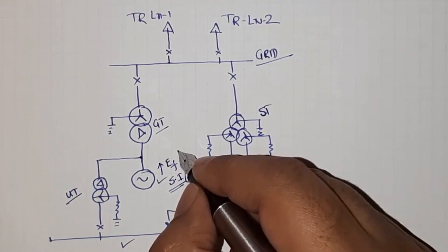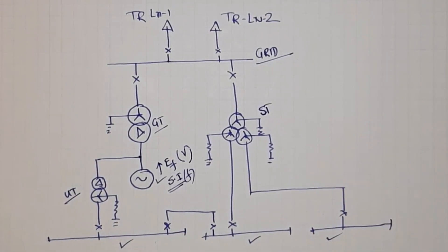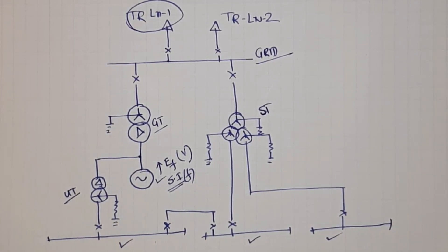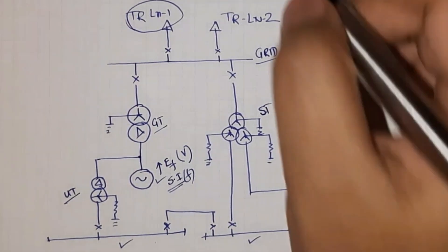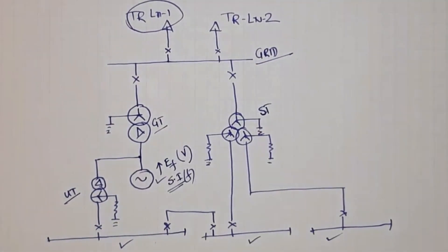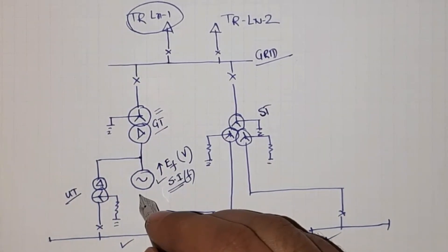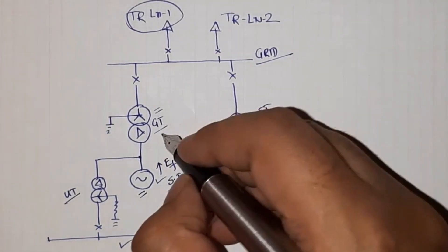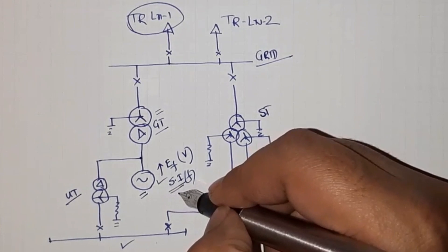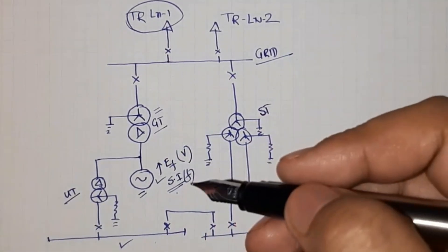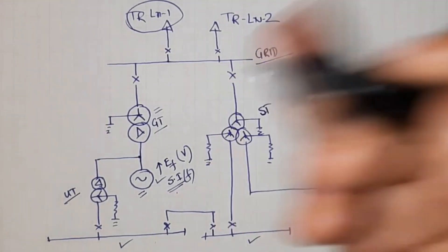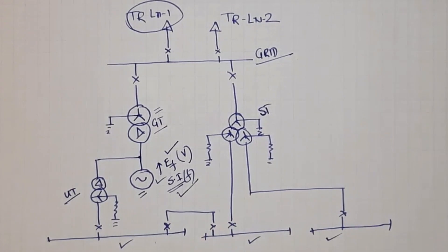A certain field voltage is set to maintain the voltage value. Now, what will happen if a transmission line suddenly trips? The transmission line is heavily loaded, so if one line is suddenly tripped there will be a huge load reduction on the system. The generator will not immediately respond — we still have a higher amount of steam input and field excitation set for the previous load. If the load is suddenly rejected, both the field excitation and frequency input will be in excess, so the voltage will increase and the frequency will increase.